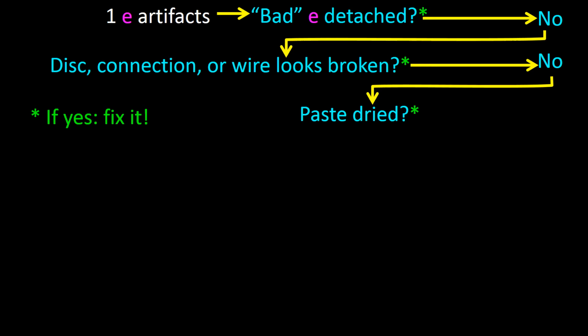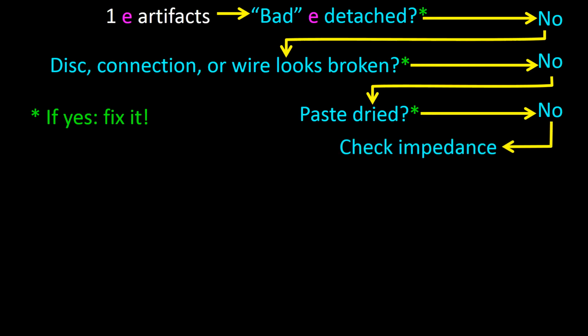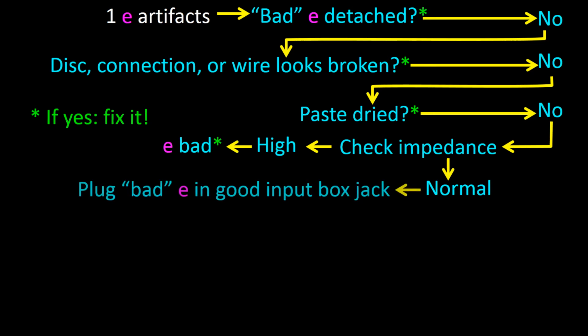see if the paste is dried, and if it is, fix it. If it is not, check impedance. If it is high, the electrode is bad, change it. If it is normal, take the suspected electrode and change it to a good spot in the jackbox. By doing so, you will have a good electrode inserted in the plug the bad electrode was plugged in before, and a bad electrode where a good electrode was there before.